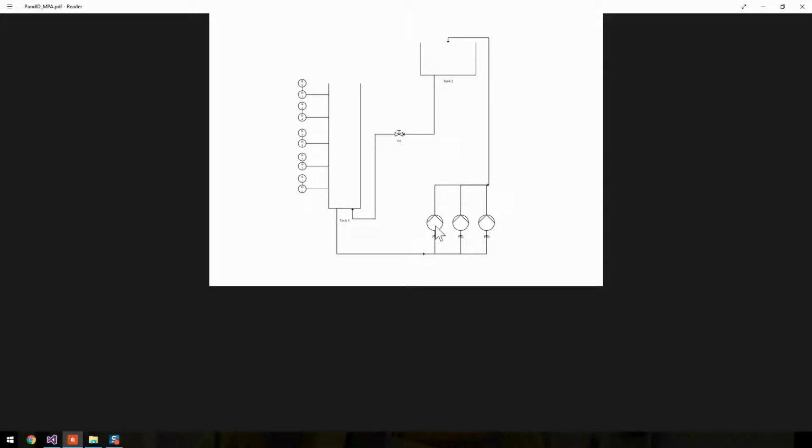By that I mean you have the local mode, where you have some kind of remote controller somewhere close to the pump, and some manual control from an HMI screen, so you can turn it on and off from an HMI screen, and an automatic mode, so it can be controlled by some other kind of PLC logic. That's 3 modes that we'd like to have. All 3 of them are included in the template blocks that we're going to use. The blocks are already made, so we'll just drag and drop and configure them.